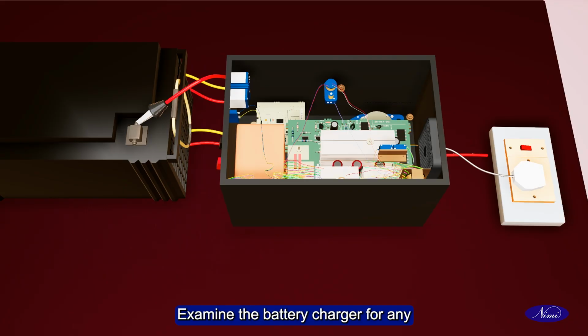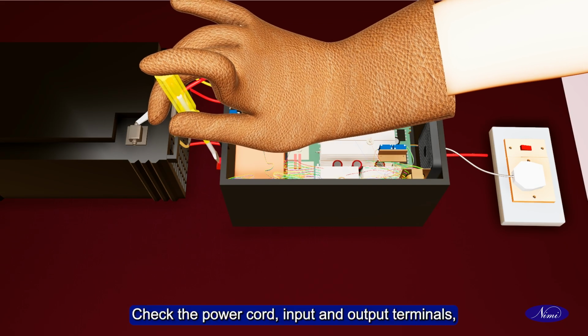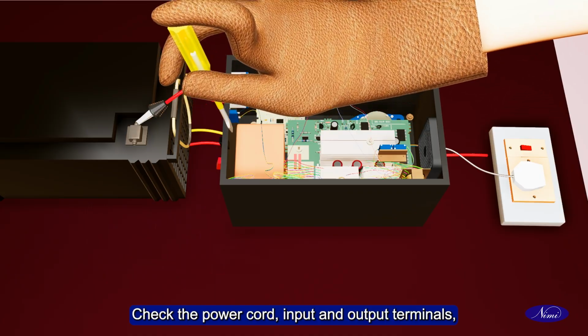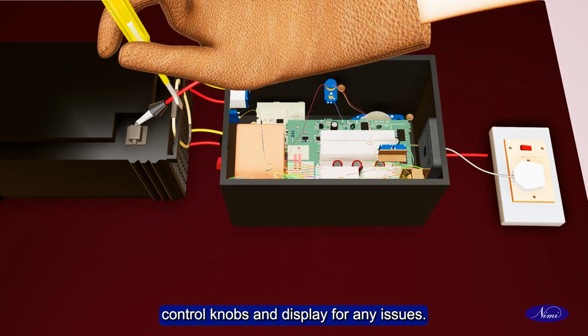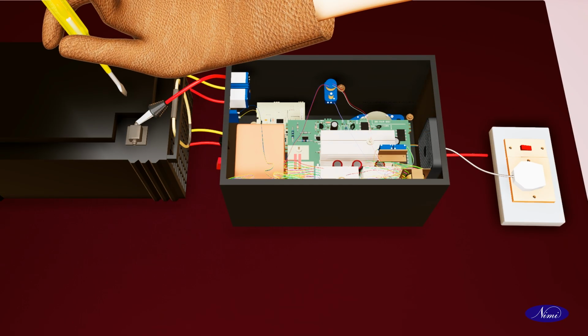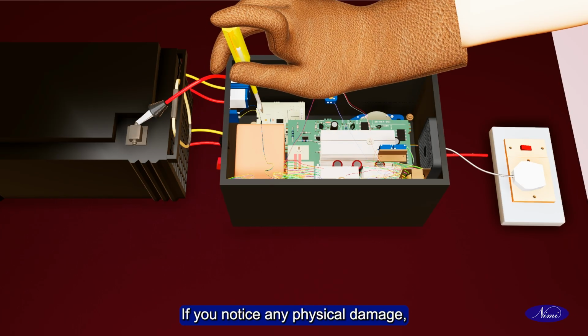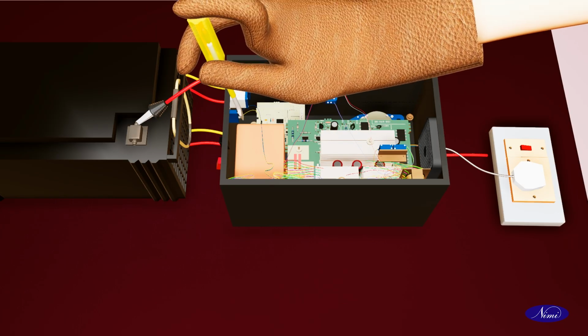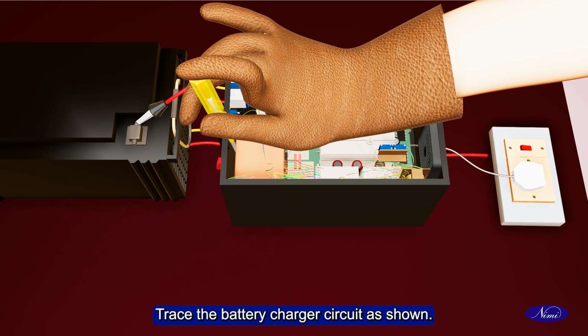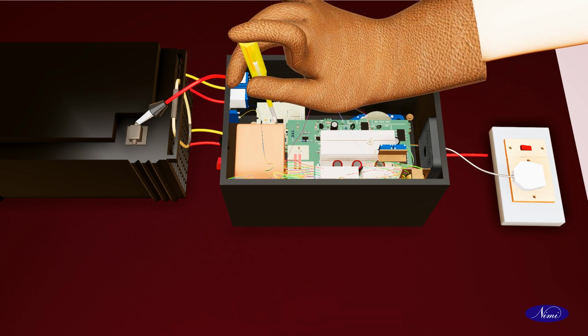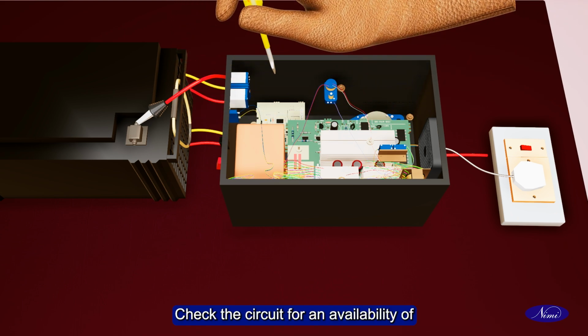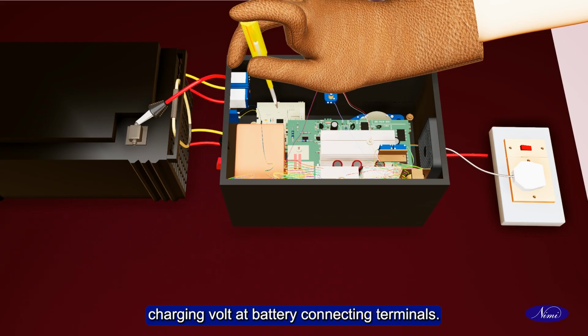Examine the battery charger for any visible signs of damage or loose connections. Check the power cord, input and output terminals, control knobs and display for any issues. If you notice any physical damage, note down the repairing. Trace the battery charger circuit as shown. Check the circuit for an availability of charging volt at battery connecting terminals. If the voltage is not available, check the fuse provided in the fuse carrier.